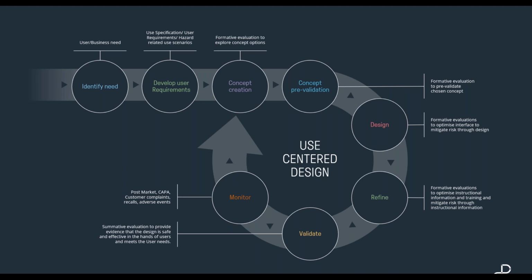So these include the use specification we discussed earlier, the 5 W's and an H, and also pull out some of the hazard-related usage scenarios. I think Louise will talk about this term a bit later. But these are essentially all those times when a user interface could inadvertently cause patient harm via a use error.